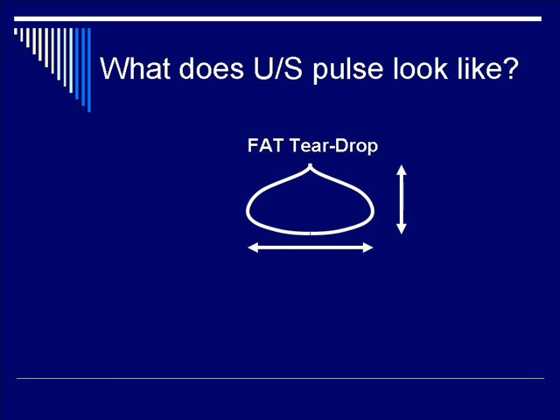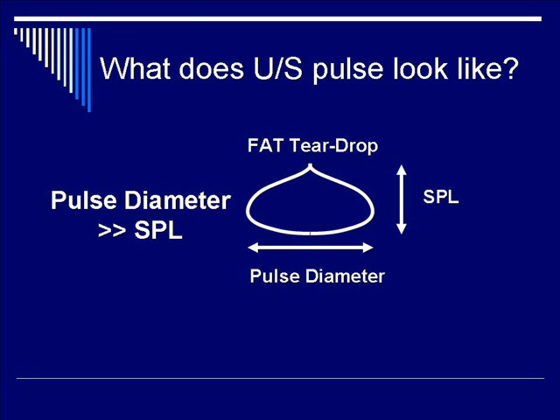Just as we can describe an ultrasound pulse in the frequency domain in terms of bandwidth or resonant frequency, or in time as a pulse duration, we can also describe an ultrasound pulse spatially — as a teardrop. A fat teardrop is an apt description of the spatial ultrasound pulse in two dimensions. You have the horizontal dimension, which is the pulse diameter, and the vertical dimension, which is the SPL or spatial pulse length. In general, the pulse diameter is much greater than the SPL. Since SPL is proportional to pulse duration, pulse diameter is much greater than pulse duration.